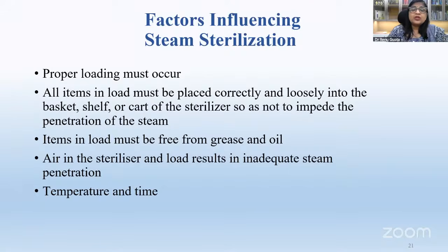All the items in the load must be placed correctly and loosely. All the instruments which have hinges should be opened up, because we want the steam to come in contact with each and every surface of the instrument. Items in the load must be free from grease and oil. I already told you, because steam cannot penetrate grease and oil. Air in the sterilizer and load must be removed fully, otherwise it will lead to a steam-air mixture and it will not bring about proper sterilization. Time and temperature are very, very important.